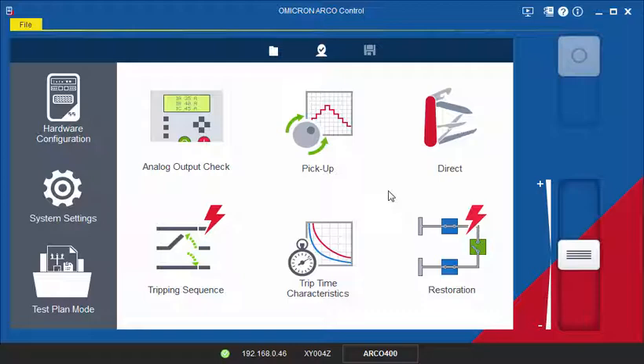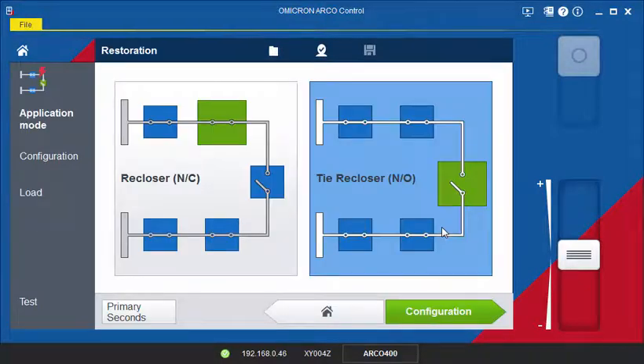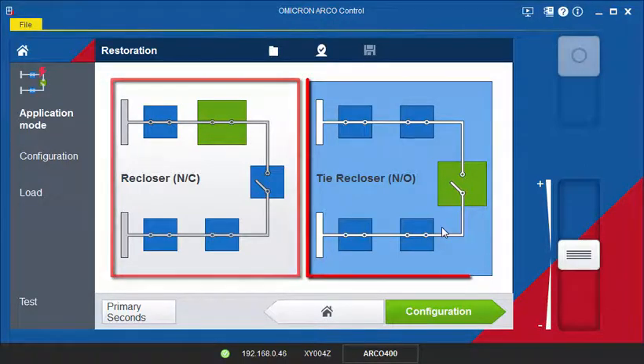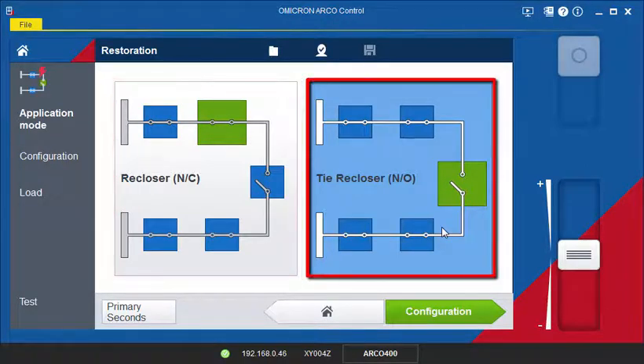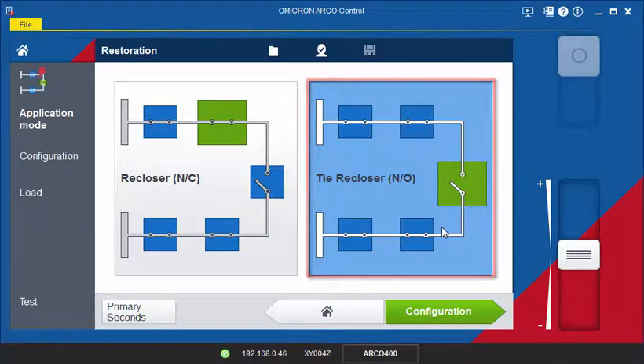The purpose of the tool is to test controllers with voltage-based automatic restoration logic. It can be used to test the correct behavior of line or midpoint reclosers as well as tie reclosers by simulating up or downstream reclosers.